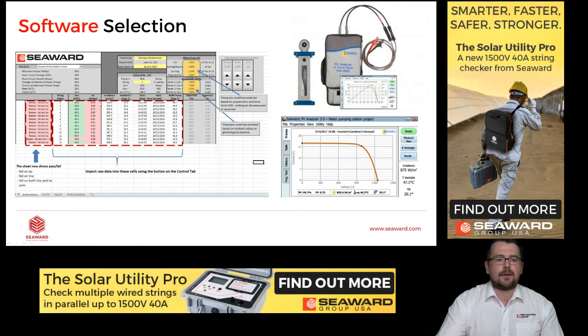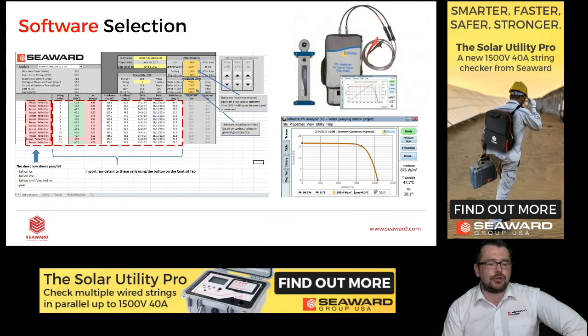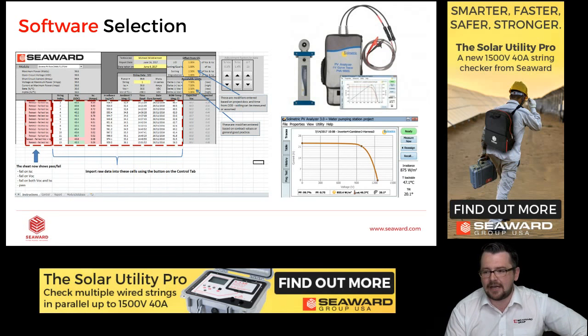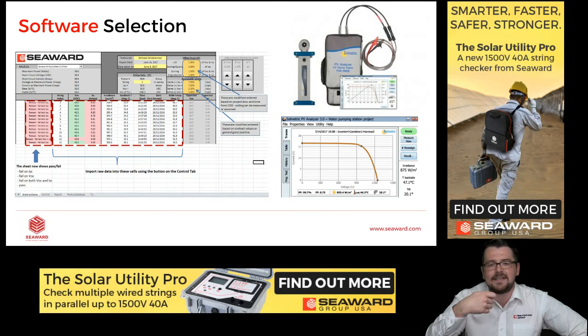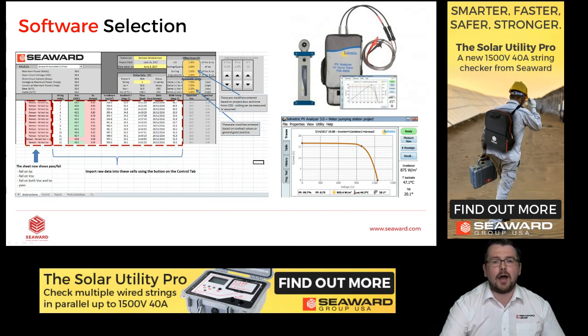So also we should be familiar with the software that we're going to use prior to getting on site. At Seaward we have a couple of options with regard to software, and I'm not going to cover these in any great detail, but also Solmetric have a very, very good software tool, the PV analyzer. These will generate STC curves, power curves, nominal curves. They will give us intelligent reporting on what the system thinks is wrong with the string. So I do advise before getting on site, familiarizing yourself with the software that you're going to use. Free training is available on all these software packages if you purchase your instruments from Seaward Solar.